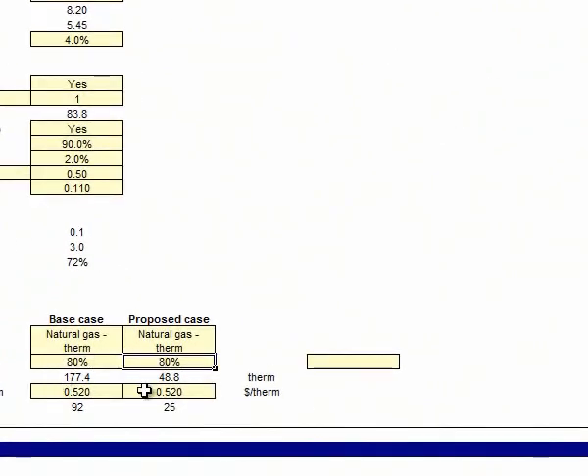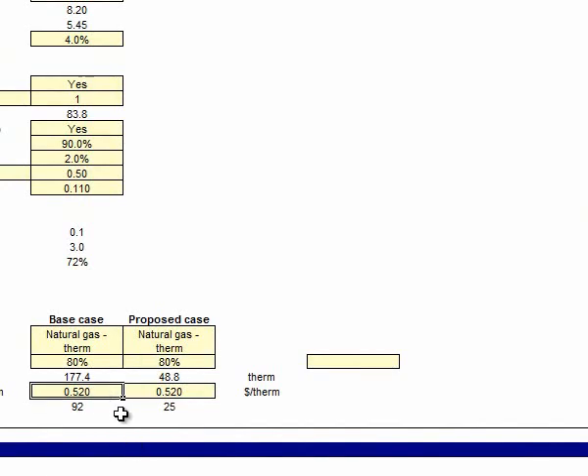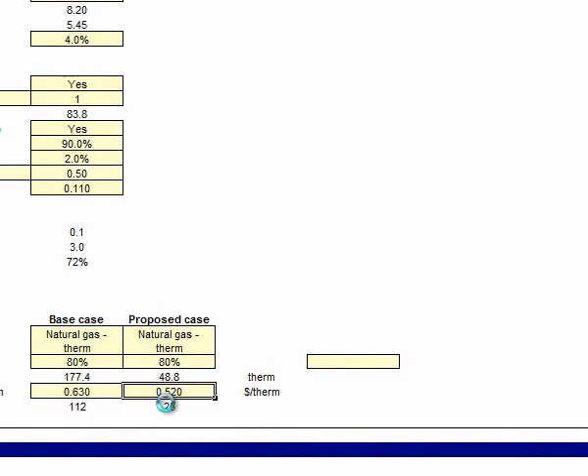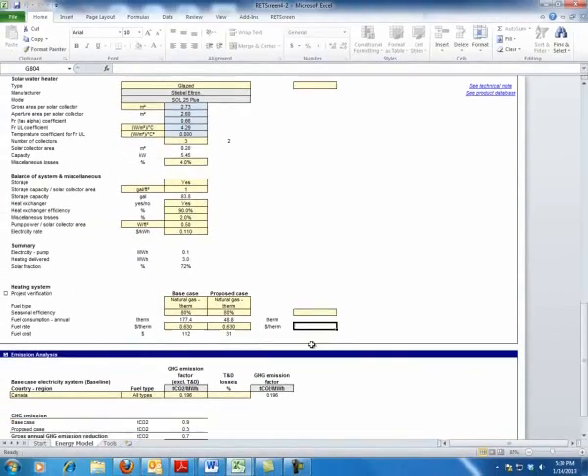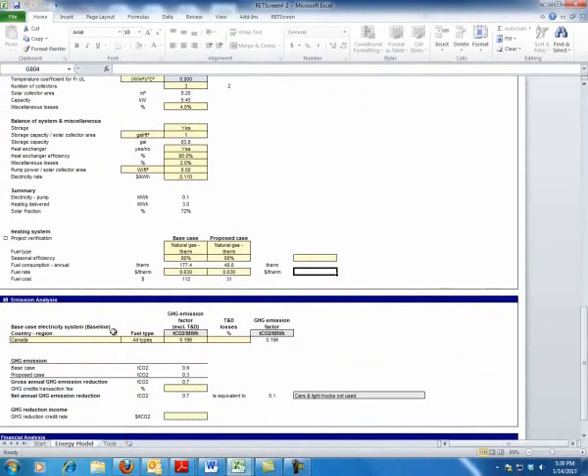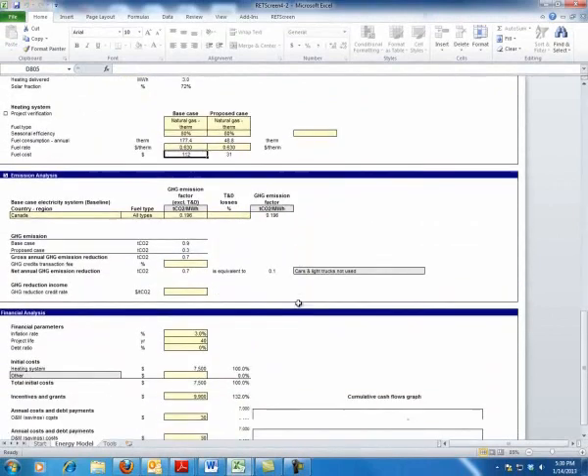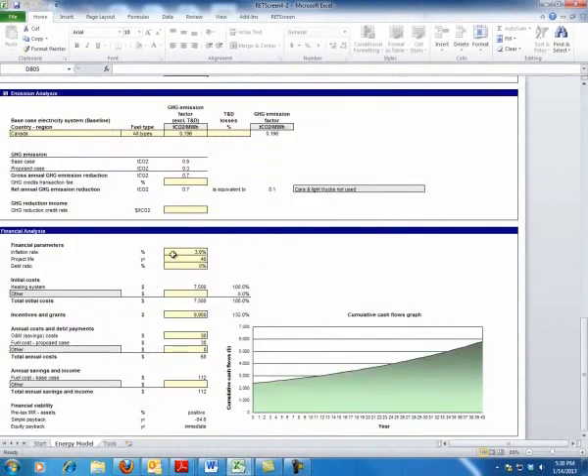I think realistically I could pull 3 off for that $7,500 to get 72%. We're going to keep it still at efficiency rating of 80%. That means how much can we convert that natural gas to heat of the hot water and how much can we save by doing that. I'm going to raise this value up to $0.63 a therm. That would include some delivery costs and everything else. So let's just make it a little more costly, but just in lines of what we're doing. So we would have a fuel cost per year, look at that, of $31 as opposed to $112.